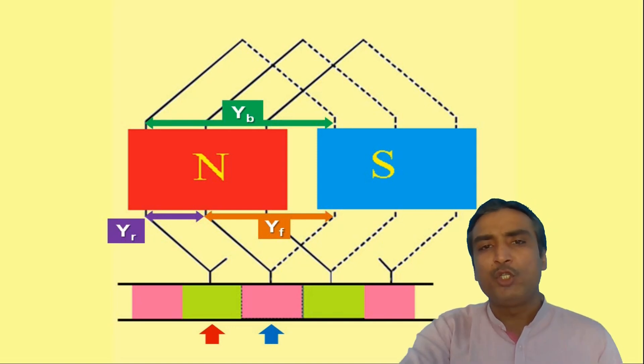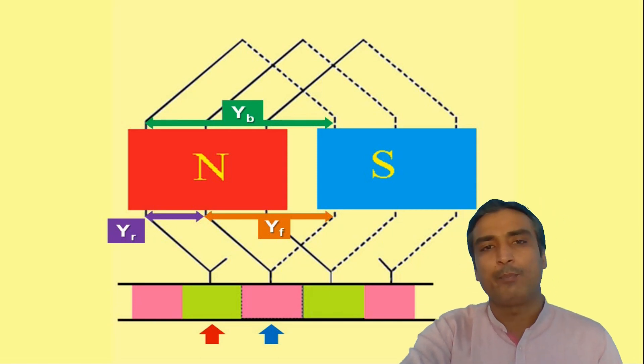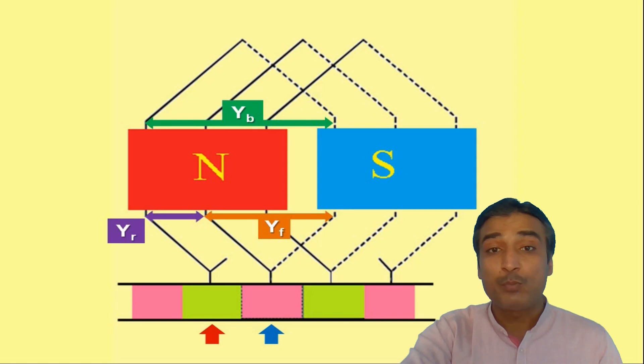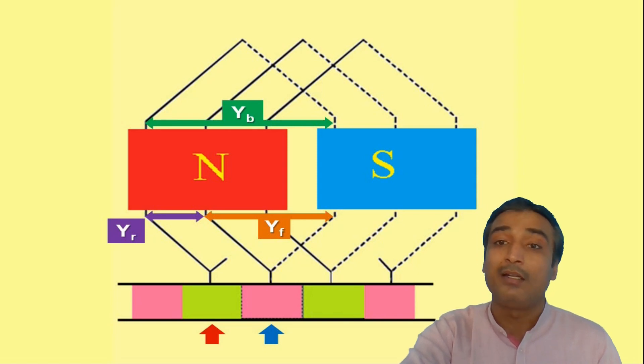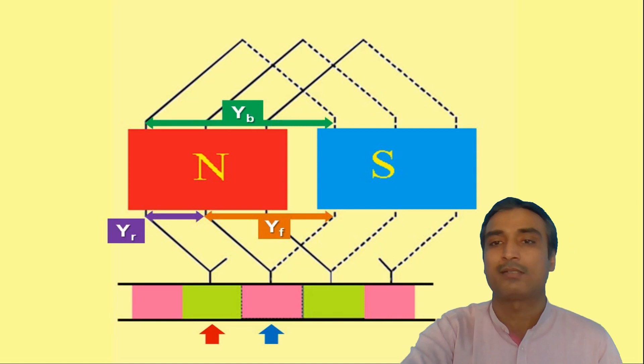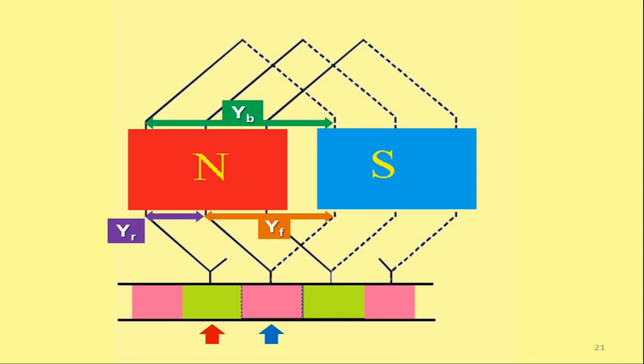Although we made use of the number of armature slots for defining the back pitch, front pitch, and resultant pitch, these pitch definitions can also be stated in terms of armature conductors. Another important term is commutator pitch, defined in terms of the number of commutator segments. It is the distance between the commutator segments to which the two ends of a coil are connected, and is generally denoted by YC.